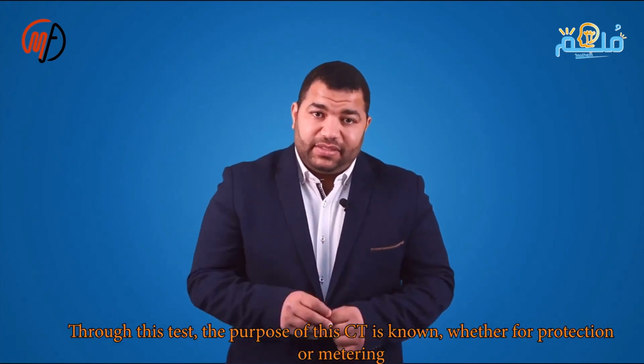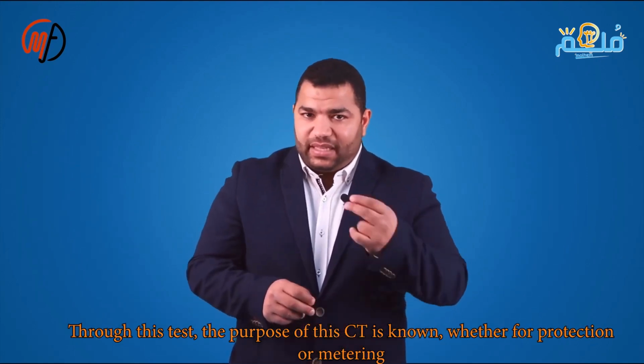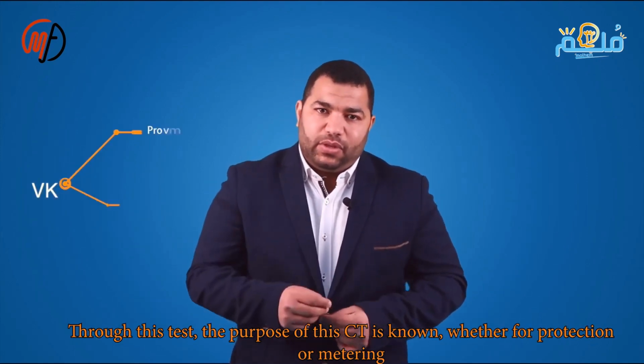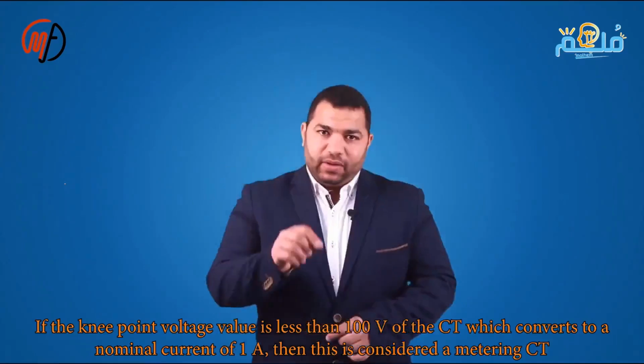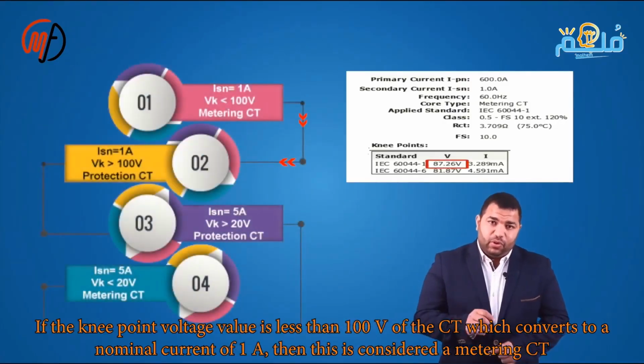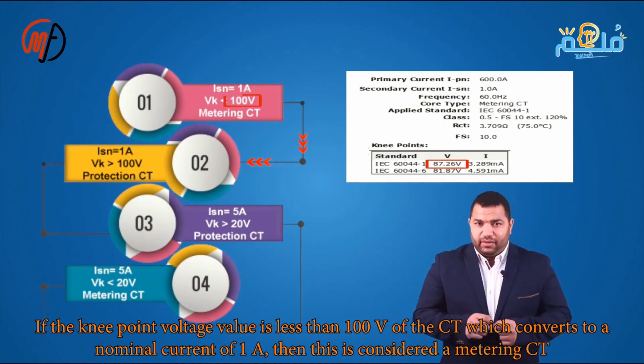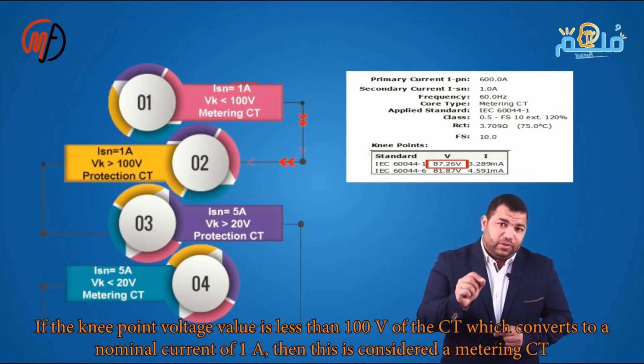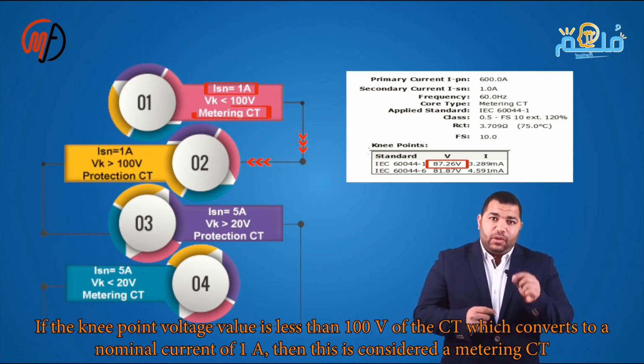This test determines if the CT is for protection or metering. If the knee point voltage is under 100 volts for a CT with a 1 ampere secondary current, it's a metering CT. If over 100 volts, it's a protection CT. For a CT with a 5 ampere secondary current, the knee point voltage is over 20 volts for protection and under 20 volts for metering.